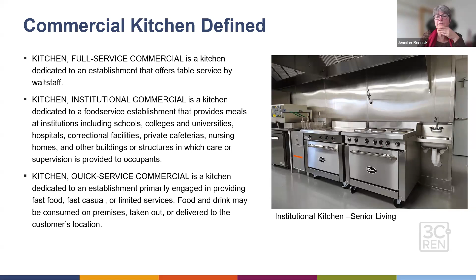But right now, the commercial kitchens have to meet the requirements, and it's for the quick service commercial kitchen and the institutional commercial kitchen, not the full service. And with these, one way is to make sure you have a 50 amp minimum, and your electric panel would have an 800 connected amp minimum, and the electric service panel should be sized to accommodate either the 208 or the 240 volt 50 amp breaker, but that's really kind of a minimum.